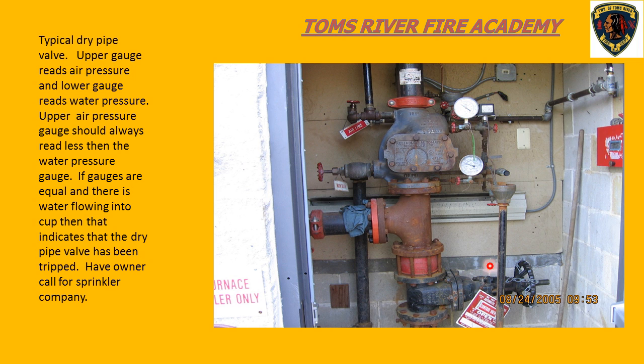Things you see here, we have an OS&Y valve, shut the water off. We have a pressure gauge that's telling us what the water pressure is on the street side of the system. This is an air pressure gauge. This is telling us what the air pressure is on the system itself. This other piping over here goes back to the air compressor. We have an air compressor that constantly maintains a specific air pressure on the system.